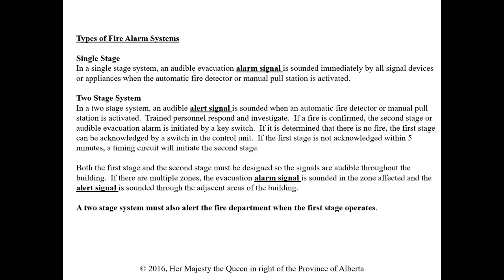In a two-stage system, trained personnel with a key can go to the pull station that was triggered and use the key switch to acknowledge the alert. If it's determined there is no fire, the first stage can be acknowledged by that switch. If the first stage is not acknowledged within five minutes, a timing circuit will automatically initiate the second stage — the full alarm — so if nobody is available to address it, everyone evacuates.